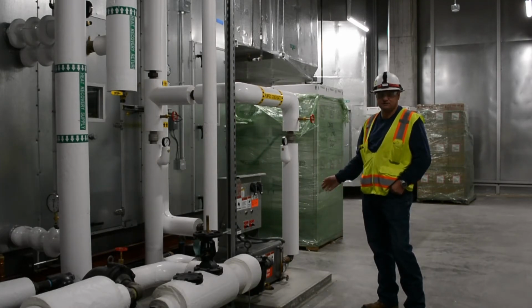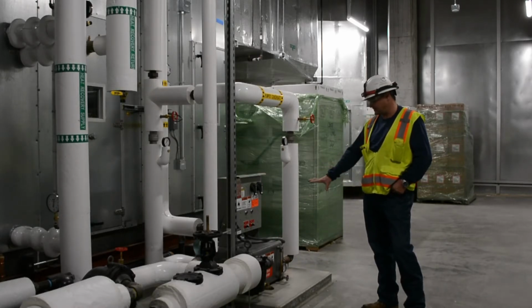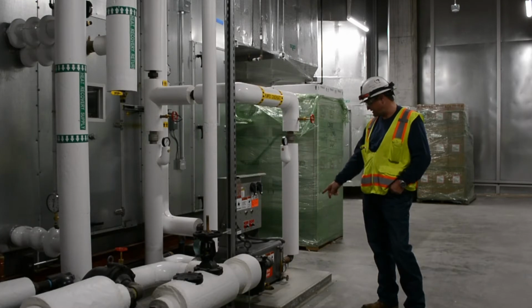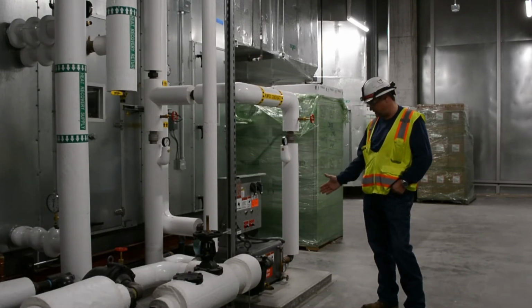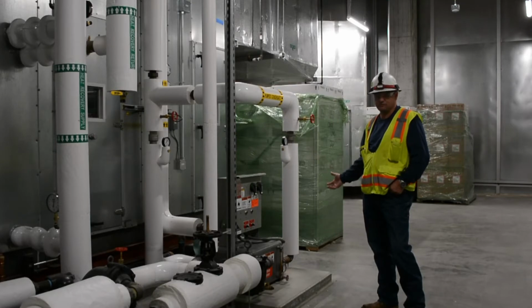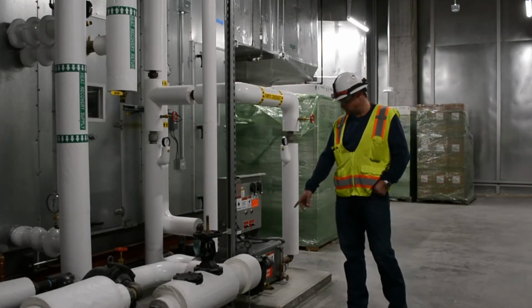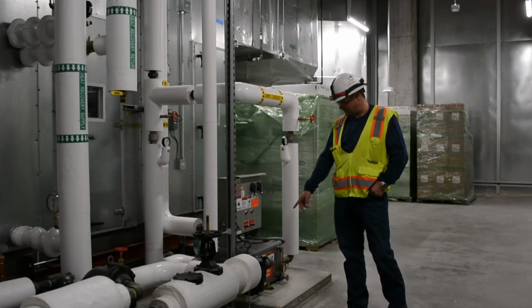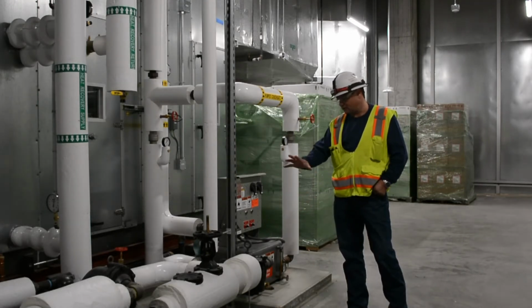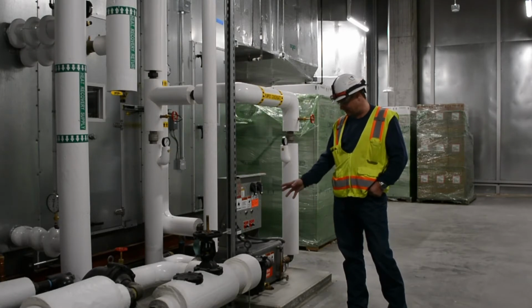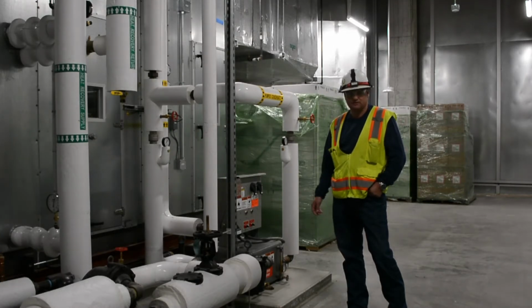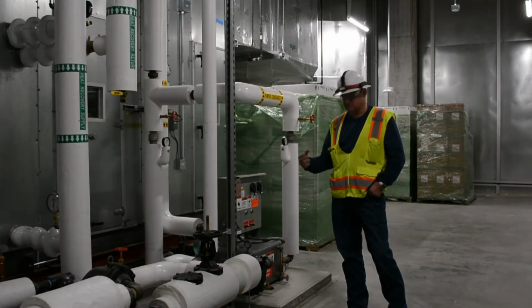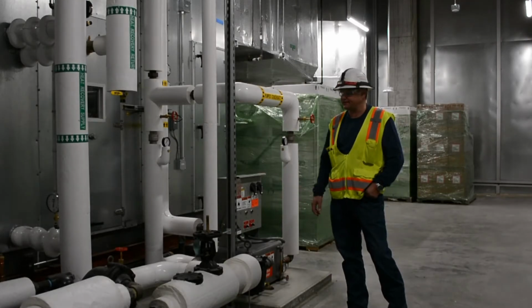The best practice on repairs for this is just to replace the pump in its entirety. The tank can stay, obviously. There is an isolation butterfly valve to isolate any existing water in the tank so that you can have easy removal of the pump and easy replacement of the pump. Here's a basket strainer that's going to collect any debris or any manufacturing sludge, oils, stuff like that. So that needs to also be inspected. I recommend at least annually. You'll open that up, you can clean the basket, and then you can return it back into its place.